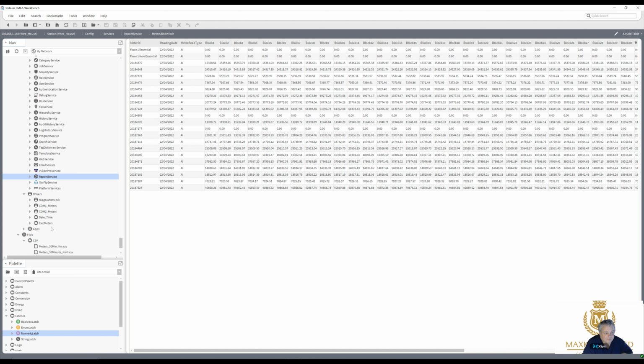And that's it, and we've put this across on quite a few sites now, but that's simple metadata via Modbus, taking the value, storing it in the numeric latch, and then the live value is being sent with the component grid to CSV, and then CSV is being FTP'd to the site.